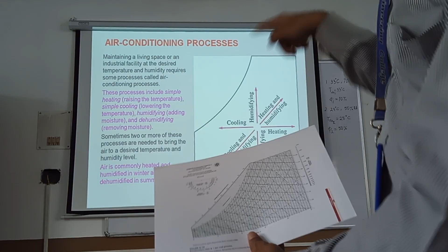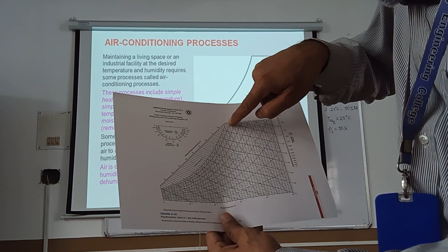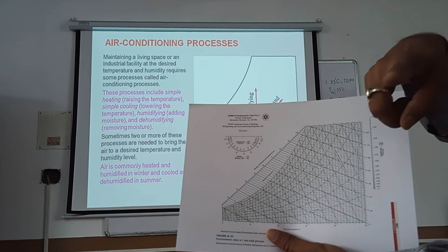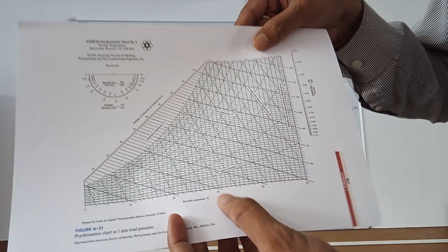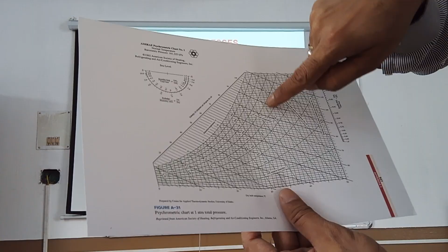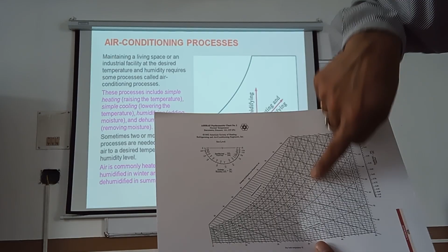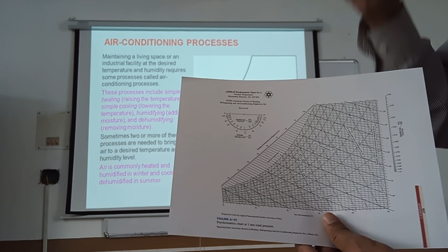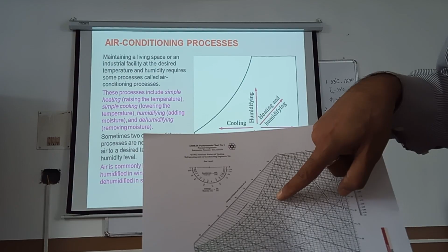Where is the first one? 33 dry bulb temperature: 10, 20, 30, here it is 33, along this line, 30, 31, 32, 33. So the 33 vertical line is the constant 33 degree centigrade dry bulb temperature line. And 70% relative humidity: you see 90, 80, 70. Where that 70 is intersecting the 33 line, that will be our current state. Clear or not? So, it is 33 in the vertical direction and following the green line, where this 70% line is intersecting, that is the state here.